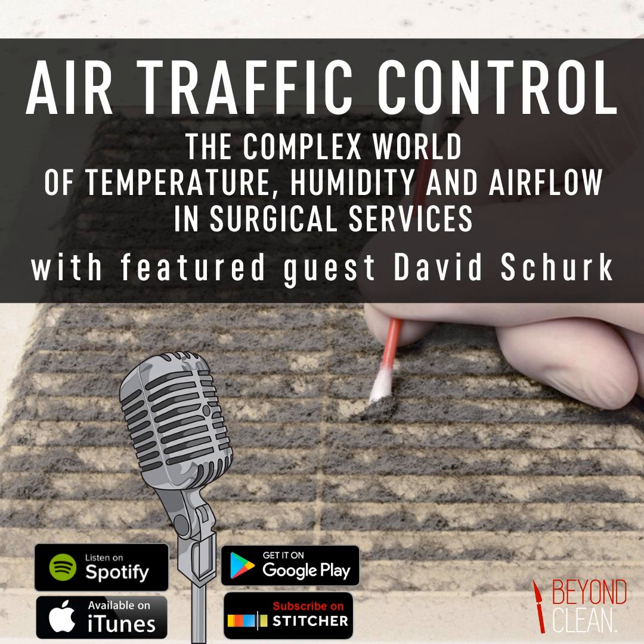But with regards to air conditioning of operating rooms in particular, that standard calls for temperatures to be maintained between 68 and 75 degrees Fahrenheit with relative humidities between 20 and 60%. Now, those are the code compliance standards that need to be followed. At the end of the day, the concept behind those is to provide environmental conditions that contribute positively to patient response and recovery. But sometimes those code requirements conflict a little bit with comfort requirements. It's also important to keep doctors and staff comfortable and to avoid humidity-related issues in the OR, like mold growth and static electric discharge. So all of that comes into play, and in a nutshell, that encompasses the importance of air conditioning for operating room environments.